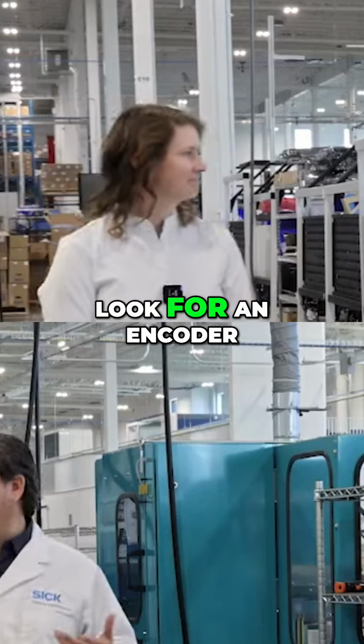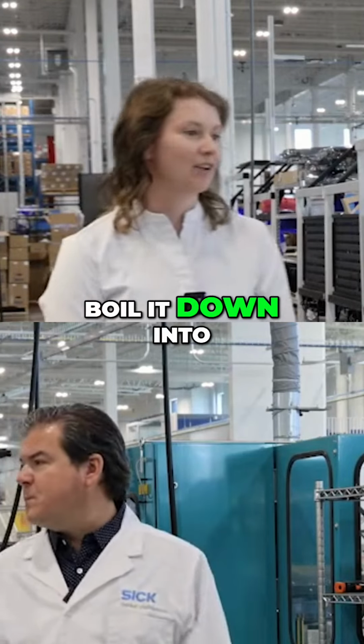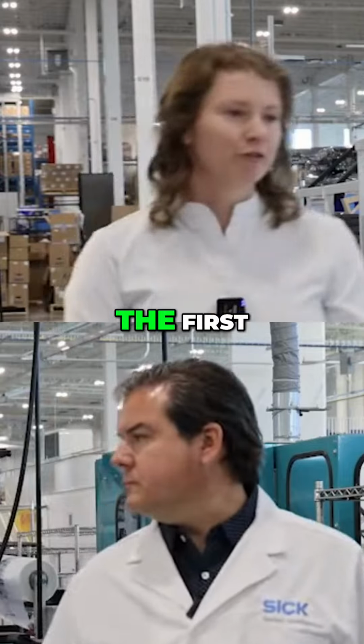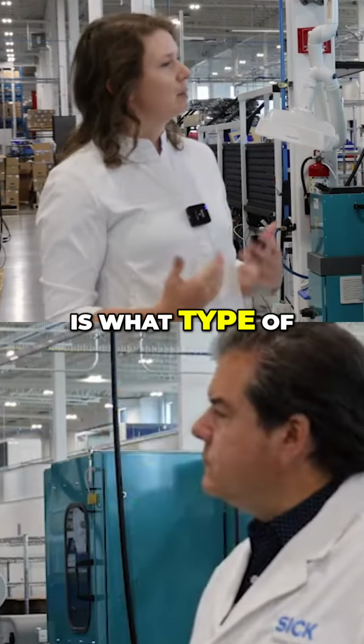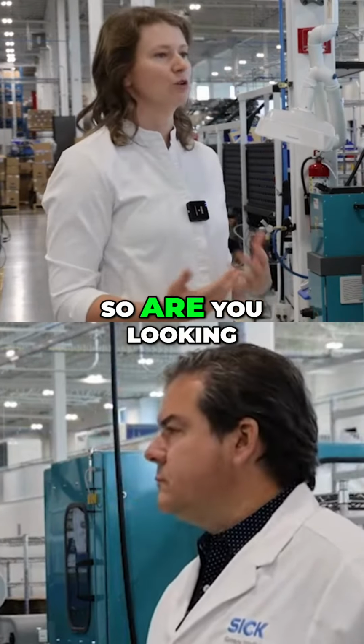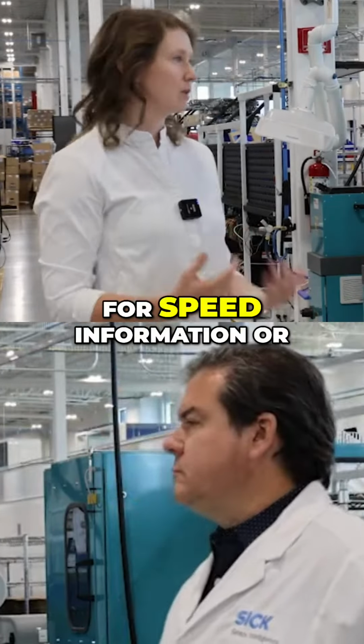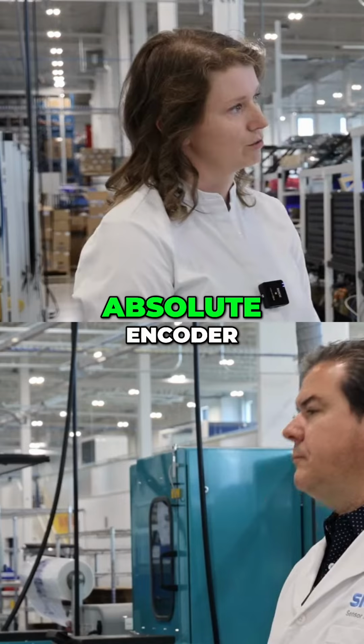All right, so what do you look for in an encoder? Yeah, so I like to boil it down into about 3 to 4 different steps. The first major step is what type of feedback you want from the encoder. So are you looking for speed information or maybe position information? That'll help you determine whether you need an incremental encoder or an absolute encoder.